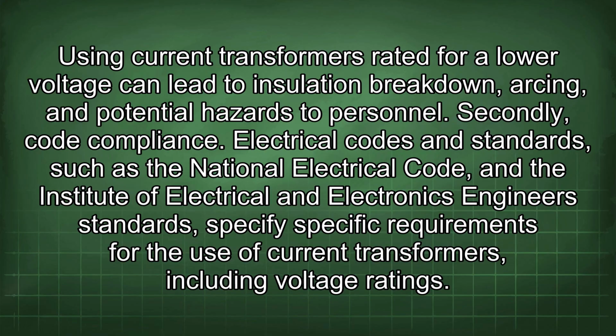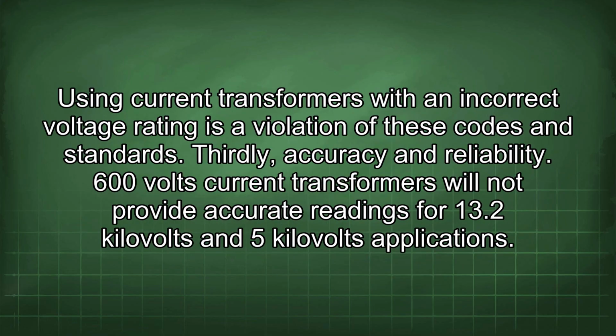to personnel. Secondly, code compliance. Electrical codes and standards such as the National Electrical Code and the Institute of Electrical and Electronics Engineers standards specify specific requirements for the use of current transformers, including voltage ratings. Using current transformers with an incorrect voltage rating is a violation of these codes and standards.